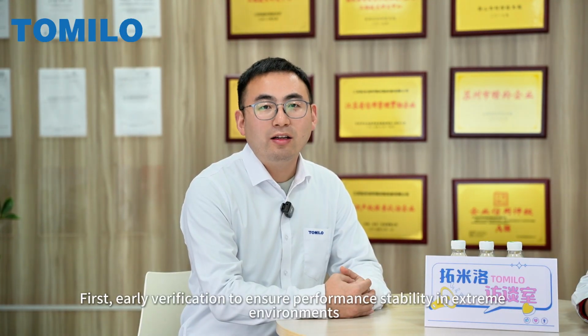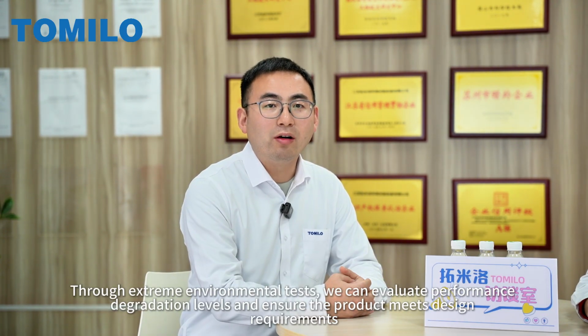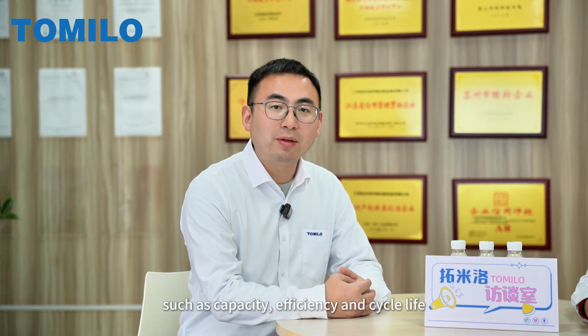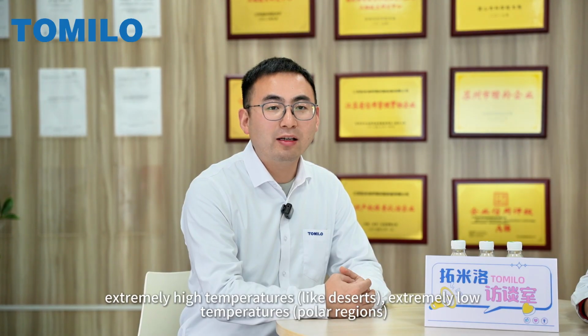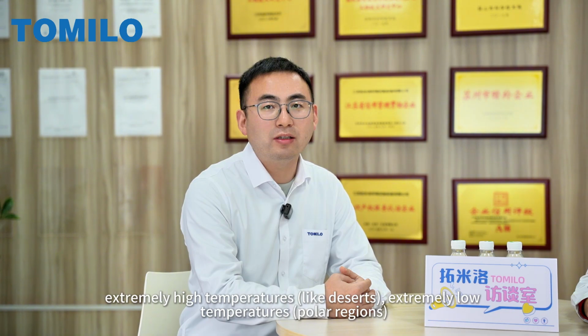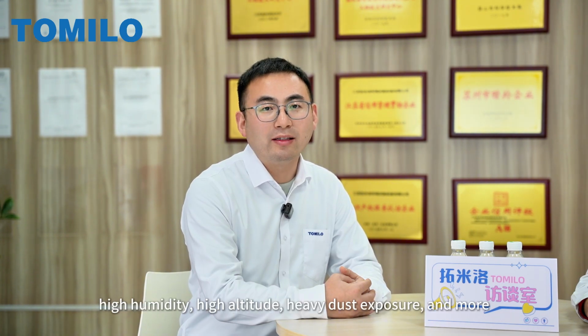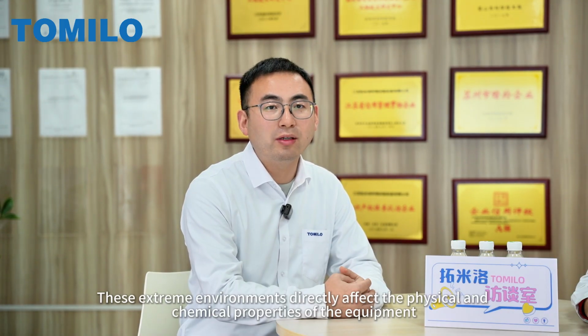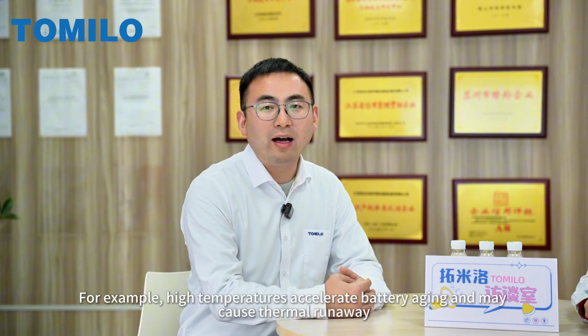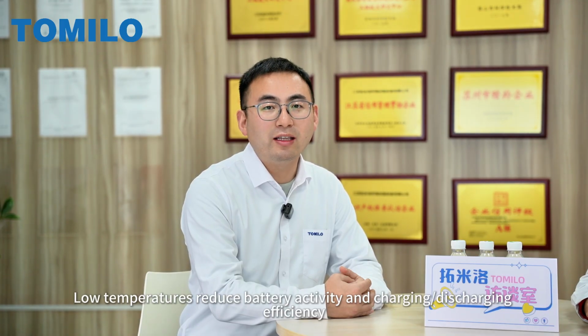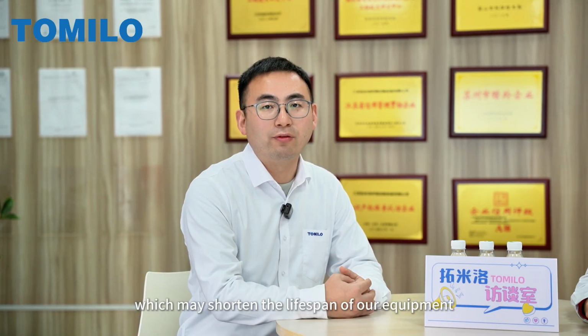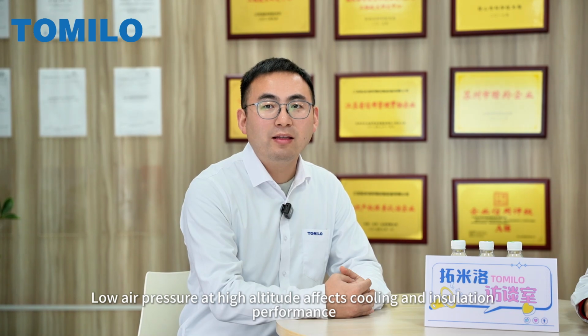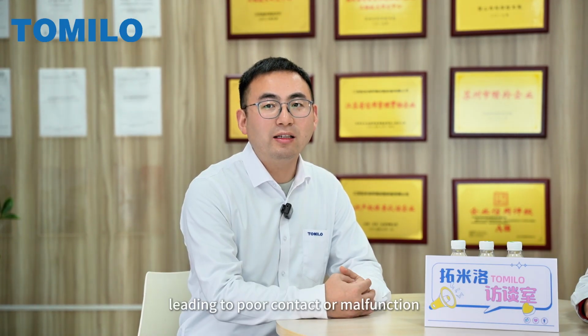First, early verification to ensure performance stability in extreme environments. Through extreme environmental tests, we can evaluate performance degradation levels and ensure the product meets design requirements, such as capacity, efficiency, and cycle life. Energy storage products may be deployed in harsh environments: extremely high temperatures like deserts, extremely low temperatures in polar regions, high humidity, high altitude, heavy dust exposure, and more. These extreme environments directly affect the physical and chemical properties of the equipment. For example, high temperatures accelerate battery aging and may cause thermal runaway. Low temperatures reduce battery activity and charging or discharging efficiency. High temperature and high humidity environments can lead to internal short circuits or corrosion of metal components, which may shorten the lifespan of our equipment. Low air pressure at high altitude affects cooling and insulation performance. Dust may clog our cooling channels, while vibrations can loosen our connecting components, leading to poor contact or malfunction.